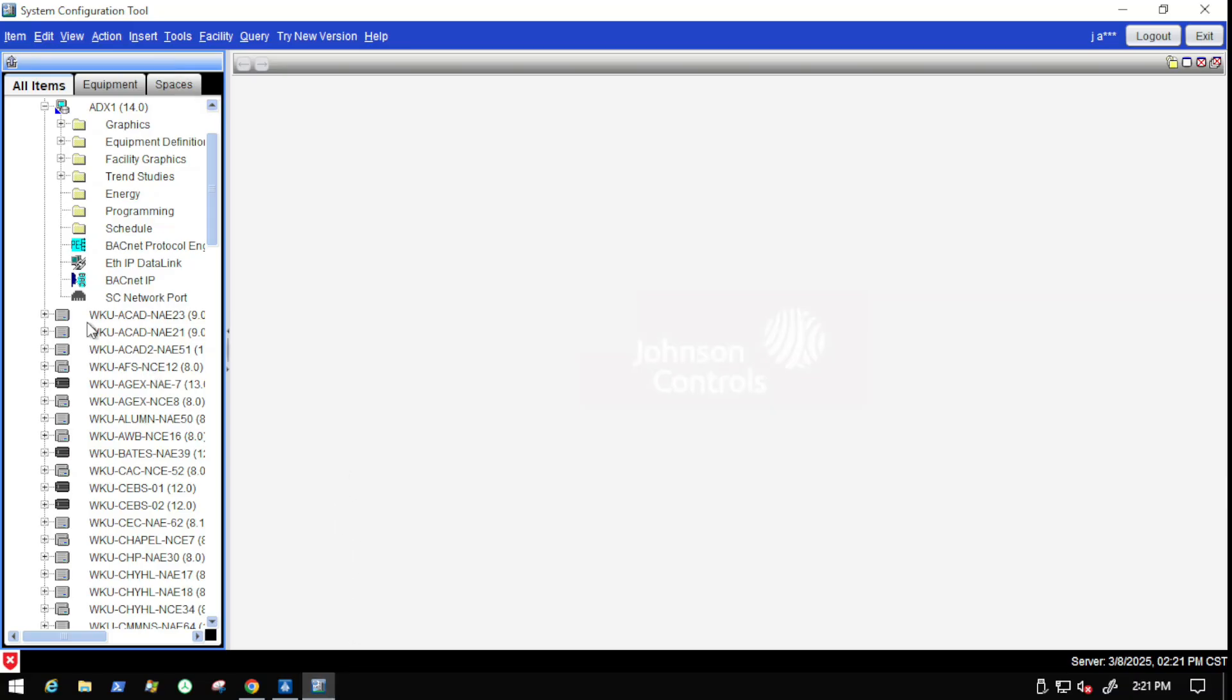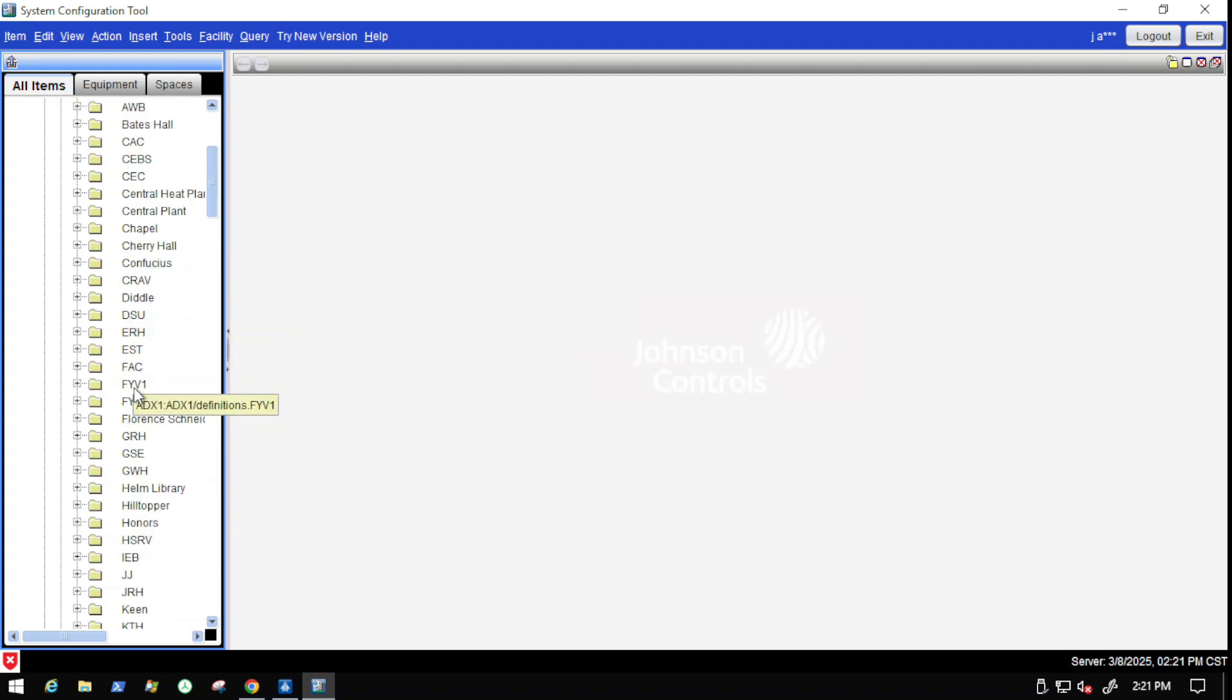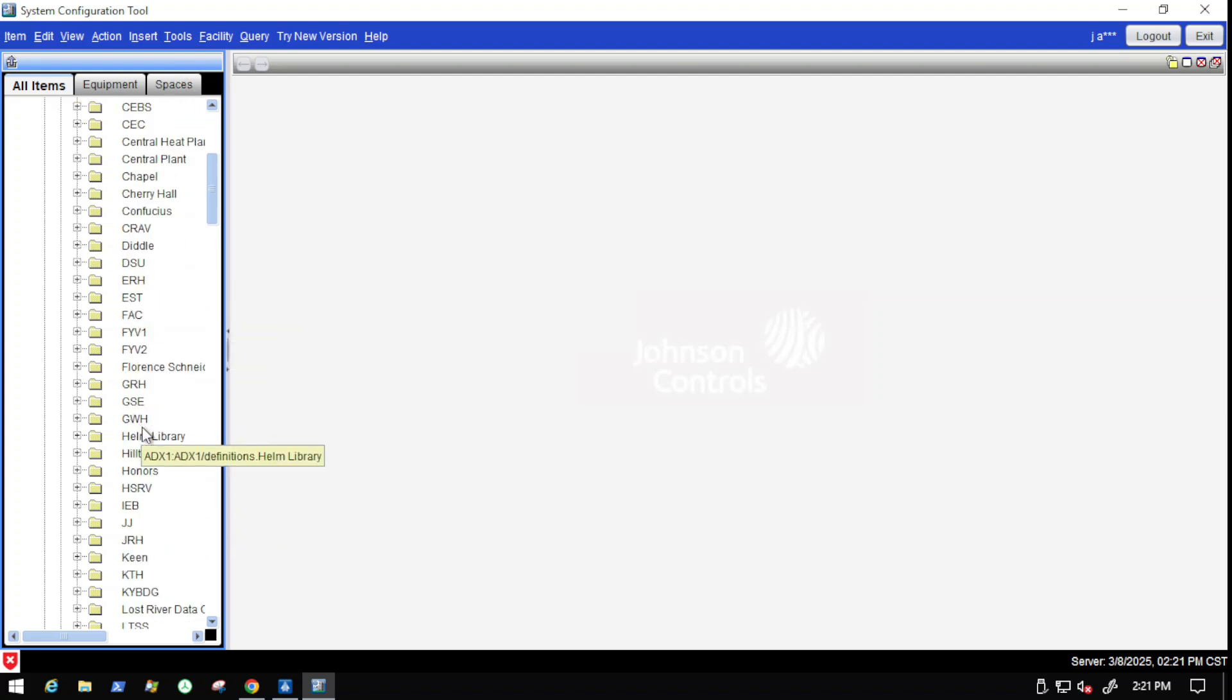So let's jump over to SCT. I've got it up here. Now for those of you all who do not know, your equipment definitions must be contained in the equipment definitions folder located on the server. That is the only place that you're going to be able to build your equipment definitions. You want to add folders and keep everything as organized as possible. I cannot stress this enough. I tell people all the time, the main thing that you have got to do is to maintain the integrity of your database. Keep it clean and it will function much better.